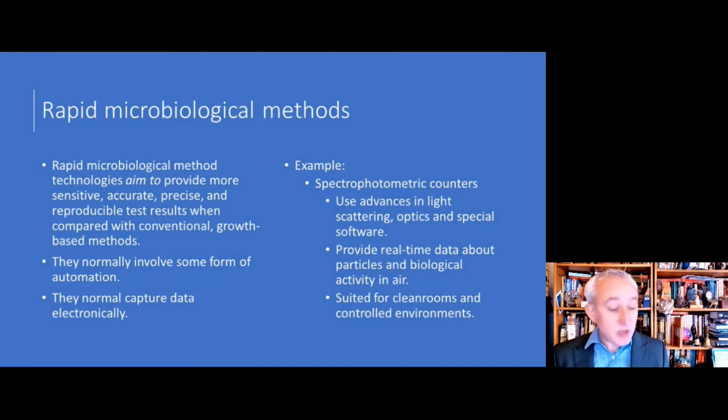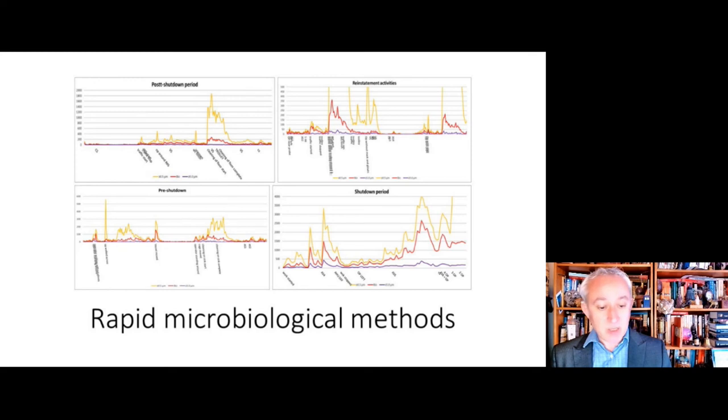To a degree, it's like a conventional particle counter. Air is drawn in and passed through a laser. These instruments count the number of particles in a sample of air. But different from a standard particle counter, they will ascertain the proportion of particles that are inert and the proportion of particles considered to be biological. This is achieved through different detectors, and biological particles are detected using a fluorescence detector looking for generally three biological markers: metabolites NADH, riboflavin, and DPA, which is found in the coat of spore-forming microorganisms. So how might this kind of technology support an environmental monitoring program? Let's look at some data from these types of systems. This is some data that I generated.